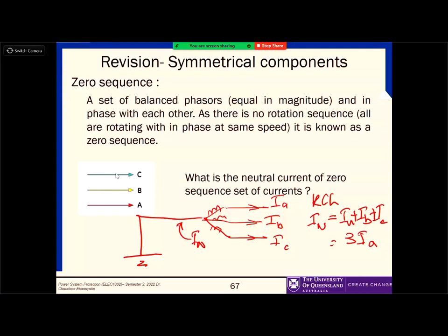So that's why sometimes, if you measure the voltage between the neutral and the earth, you can see that there is probably 40 volts, 80 volts sometimes. That is because of the unbalance of the system, right? That's at the domestic level of 240 volts. But if you are looking at 132 kV or 220 kV unbalanced systems, and when you measure the neutral voltage there is, let's say, 10 kilovolts of neutral voltage, it means there's an unbalanced condition. So it's quite easy to identify them by looking at the neutral conditions.